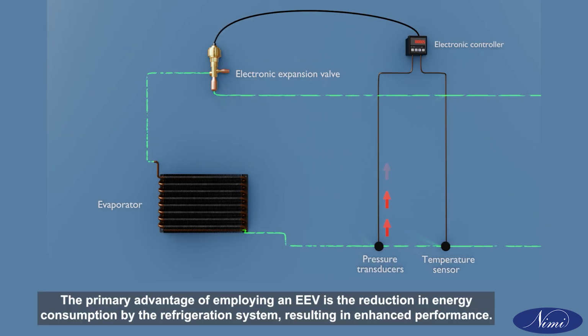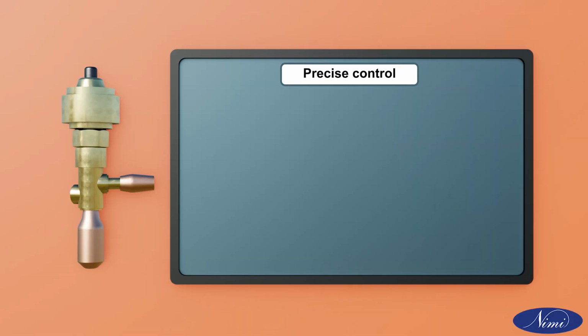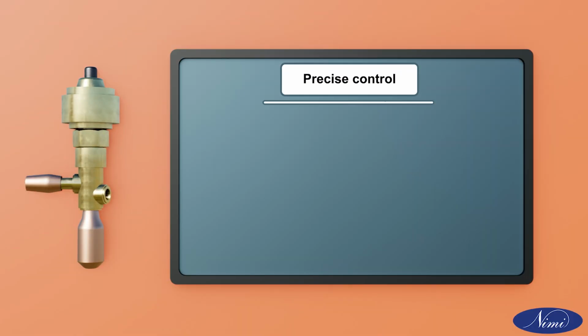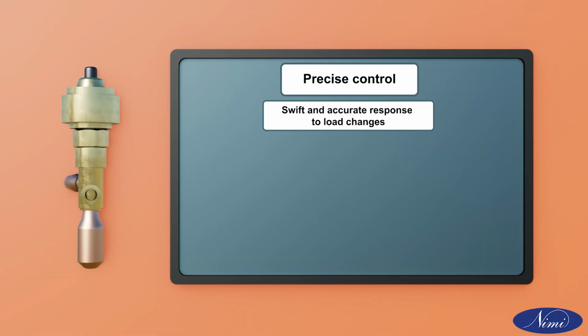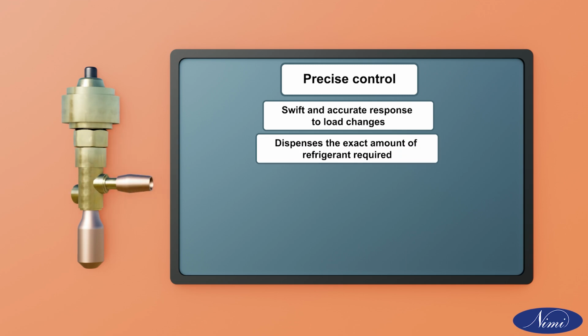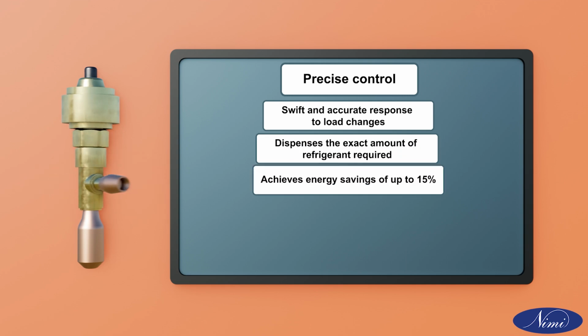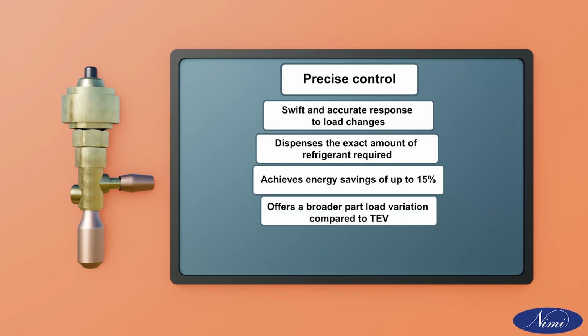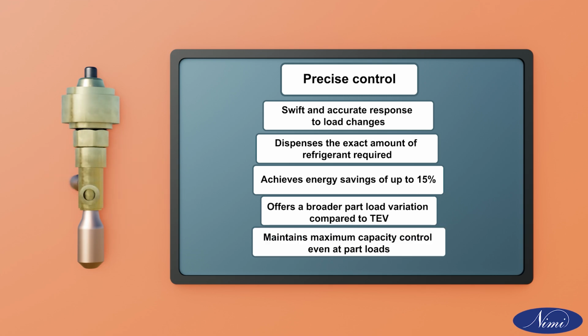The primary advantage of employing an EEV is the reduction in energy consumption by the refrigeration system, resulting in enhanced performance. Precise control. Swift and accurate response to load changes. Dispenses the exact amount of refrigerant required. Achieves energy savings of up to 15%. Offers a broader part load variation compared to TEV. Maintains maximum capacity control even at part loads.